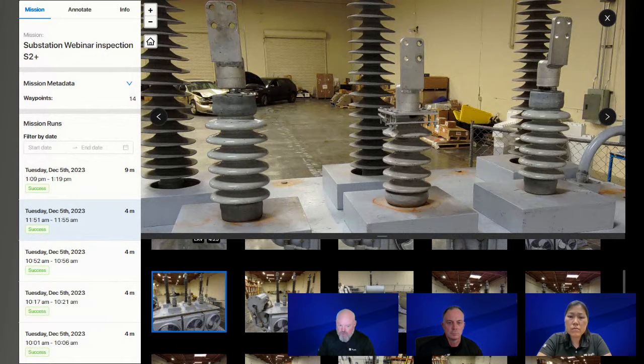That to me is super cool. Another really neat use case is the ability to do pre and post switch inspection. From my time as a distribution systems operator, when we operated switches via SCADA in the field during normal loading situations, it wasn't that big of a deal. You just operated them, then checked the amp meter to show that load was flowing the same through all three phases.